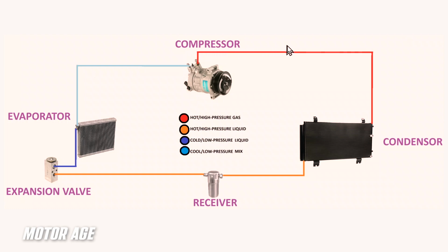But the compressor discharges the pressurized gaseous refrigerant across the condenser, where it sheds BTUs or heat energy to the air through the process of convection. And the now liquefied, hot, high pressure refrigerant collects and is stored here in this receiver as liquid, because the throttling of the expansion valve will allow more or less refrigerant to pass through the evaporator depending on heat load. But the process functions very similarly. The process of evaporation and condensation occurs very similarly in the expansion valve system as it does in the orifice tube system.